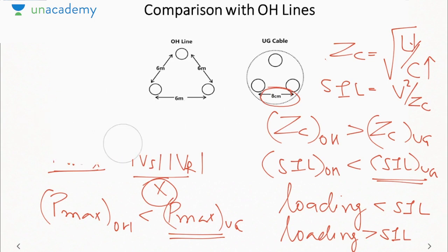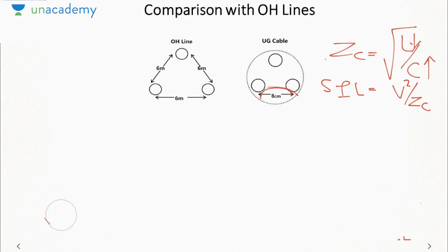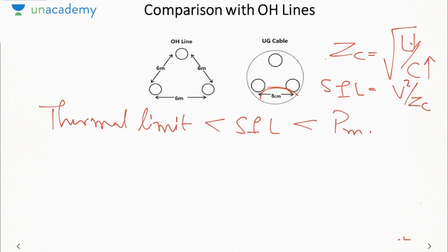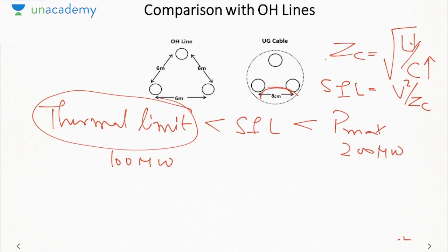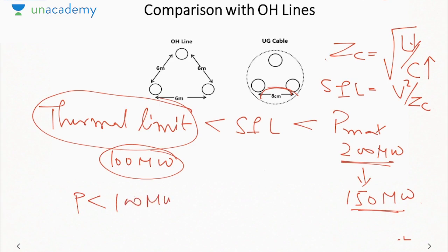What I am saying is, in this case, the limits will be arranged how? Thermal limit, then SIL, then Pmax. So we have to take care that none of the limits is violated. So we will keep loading less than thermal limit. Suppose this is 100 megawatt and this is 200 megawatt. By using a series reactor, the reactance will increase and Pmax will go down. Suppose it comes down to 150 megawatt. But already we are keeping power less than 100 megawatt. So even if Pmax reduces, that does not impact the performance of the cable, because loading is safely below the Pmax already. So that is why we can use a series reactor in case of underground cable.